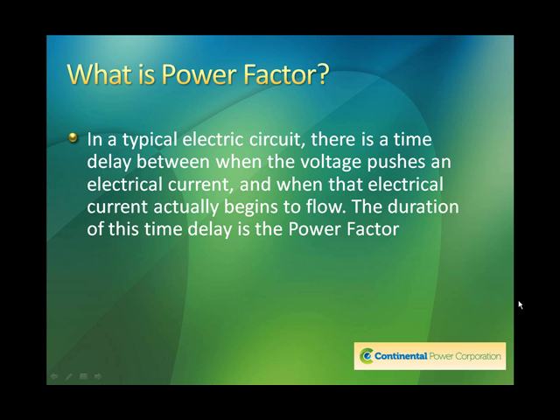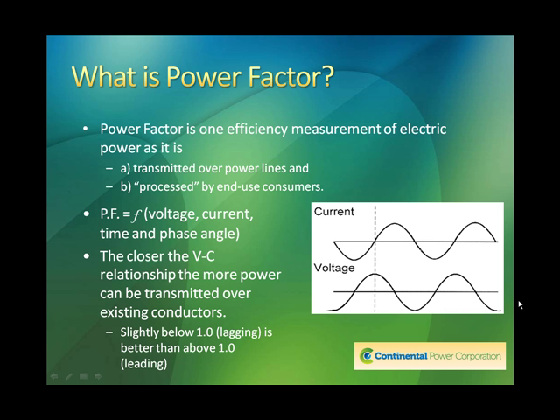Now, I know that doesn't mean anything to you, but we're going to get into some practical applications here that this might become a lot more clear. To describe it some other ways, power factor is one efficiency measurement of electric power as it is transmitted over power lines and it is processed by end-use consumers. In other words, as it is utilized. Power factor is a factor of voltage, current, time, and phase angle. The closer the voltage-current relationship, the more power can be transmitted over existing conductors. Slightly below 1, which would be lagging, is better than above 1.0 or leading.